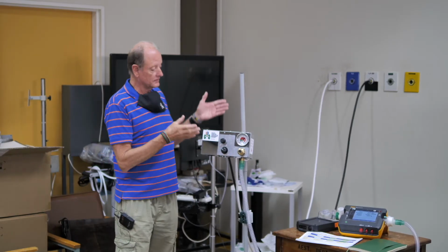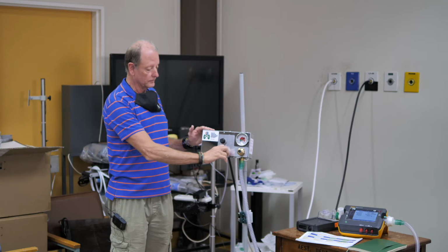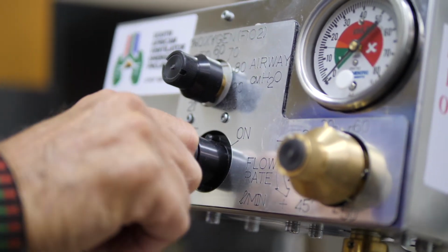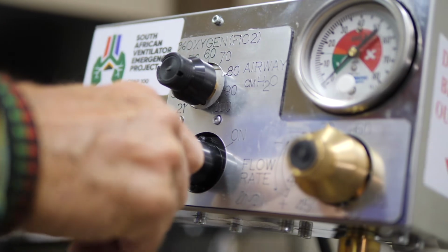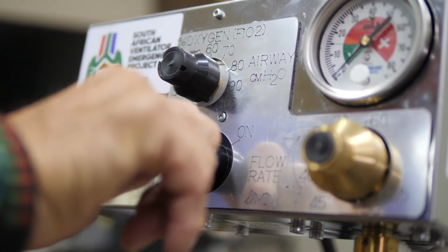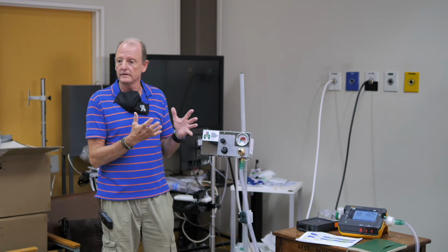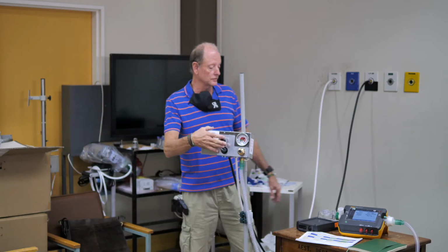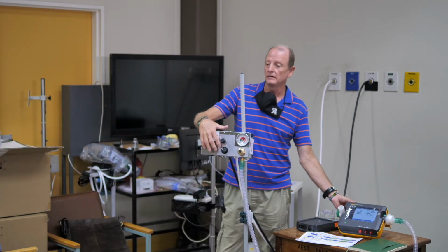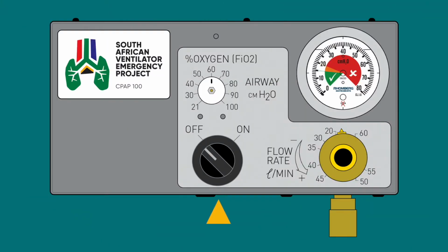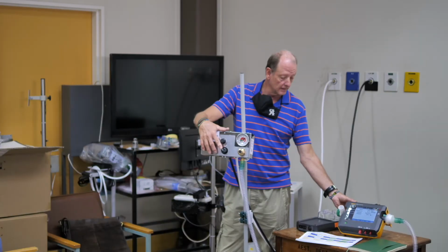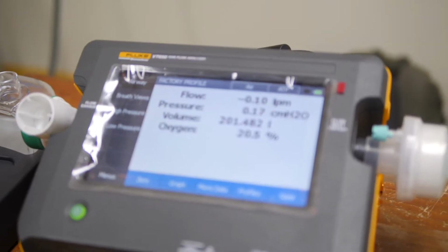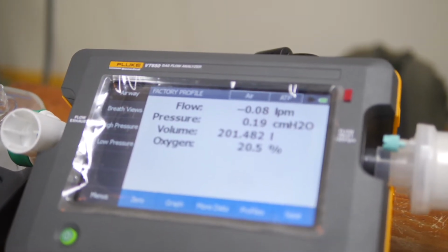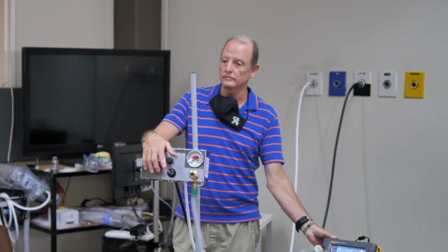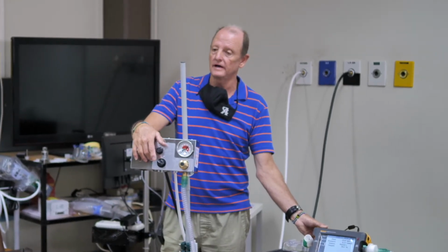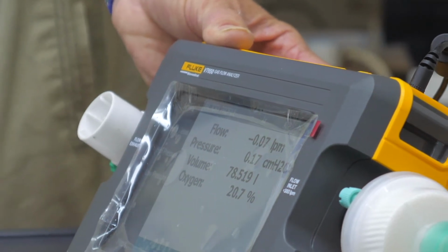When it's connected like this, what you want to do, like we've done, is switch on, switch off, just to get a flow. Don't worry about where your flow is set. You just want the unit to hear it working. When you switch it off, you'll be checking the on-off switch, that it is working correctly, that there's no leak. So when it's off, obviously you should have no flow. You are allowed a certain leak past that, very, very slight. When it's off, it's off.